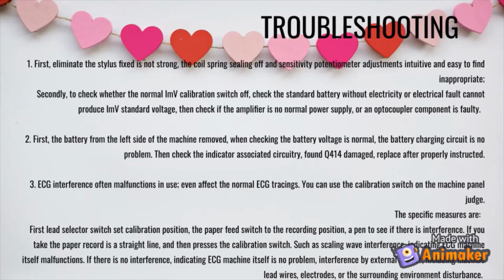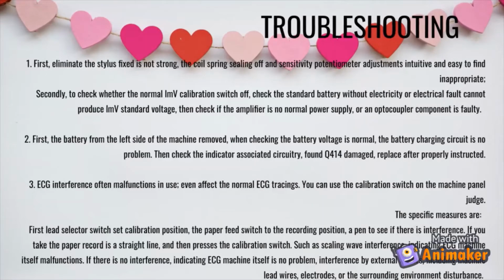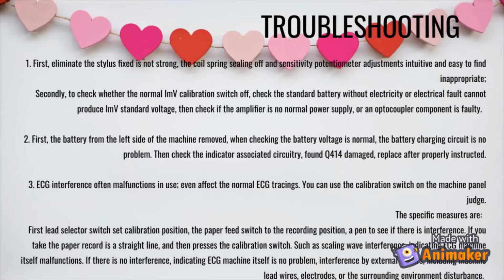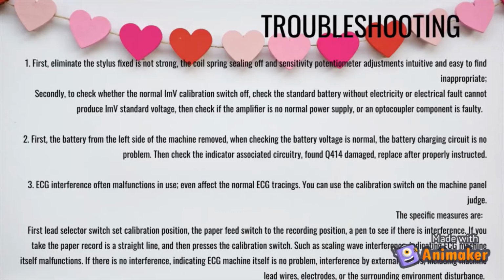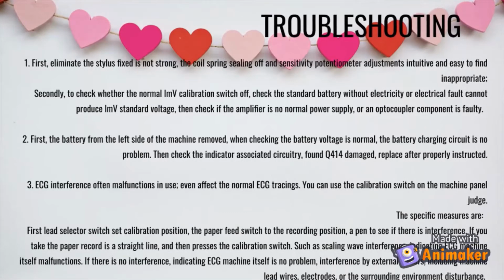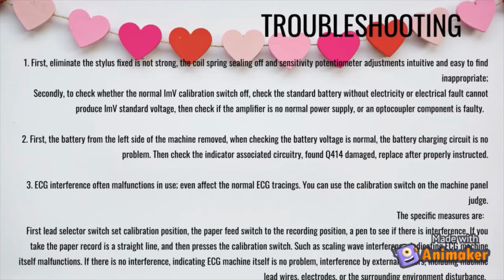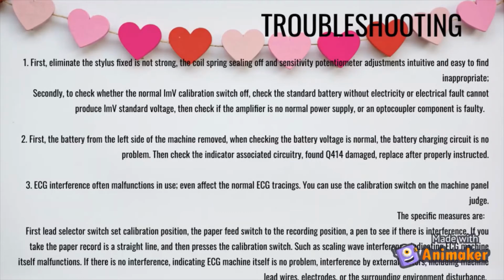Use the pen to see if there is interference. If the paper record is a straight line and then you press the calibration switch, such as a scaling wave, interference indicates the ECG machine itself is malfunctioning. If there is no interference, it indicates the ECG machine itself has no problem. Interference by external factors includes the machine, lead wires, electrodes or surrounding environment disturbance.